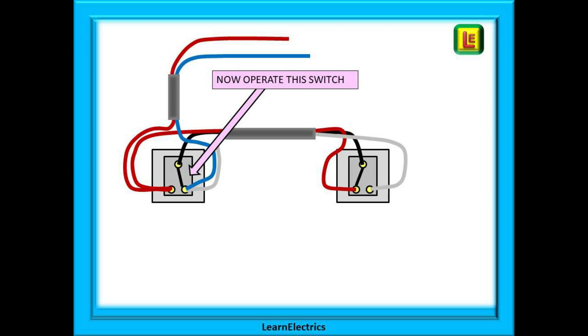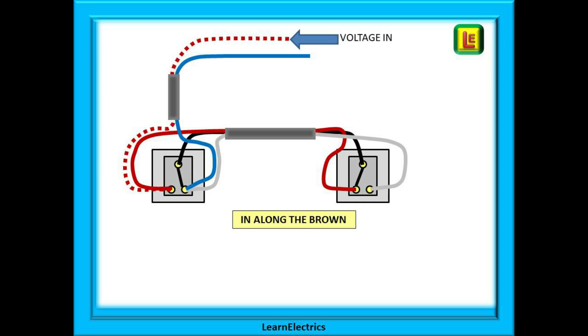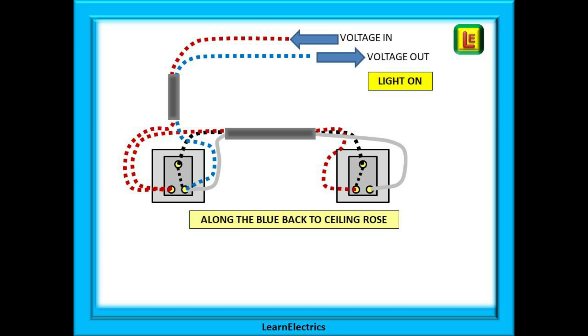Now we can operate switch number 1. And what happens this time? Voltage in along the brown switch wire to L1, along the brown wire of the strapper cable this time to L1 of switch number 2. Through the switch to the common terminal and along the black wire to terminal L2 of the first switch. Up the blue of the switch wire to the ceiling rose. Voltage in, voltage out, the light will come on.